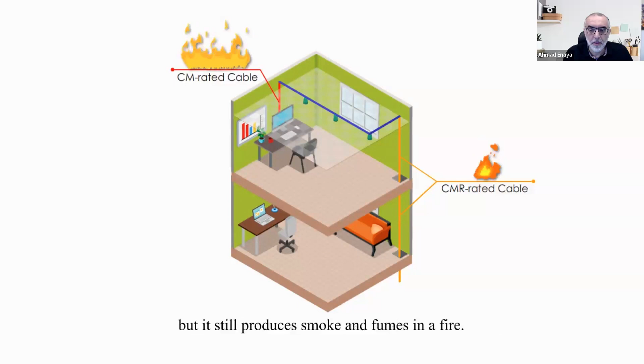On the right side is a CMR-rated cable that can be installed between floors of a multi-story building. It's better than CM-rated cable, but it still produces smoke and fumes in a fire. The best fire-rated cable is CMP-rated. So CM is a lot of fire, CMR is less fire, CMP is the least. It is normally installed in a plenum area above the drop ceiling. This is the general view. Now let me talk about each of these 3 fire-rated cables in detail.